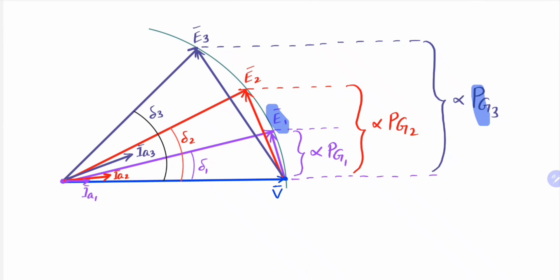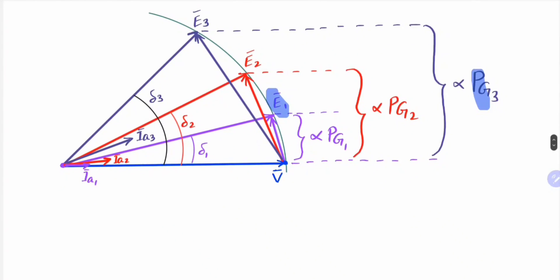Now, if we want our alternator to supply reactive power instead of consuming it, we can adjust the field current. By adjusting the field current, the alternator's reactive power output may be changed — it will start supplying reactive power instead of consuming it. So if we adjust the field excitation so that it starts supplying reactive power, then plotting further we observe that the power factor will increase instead of decreasing.